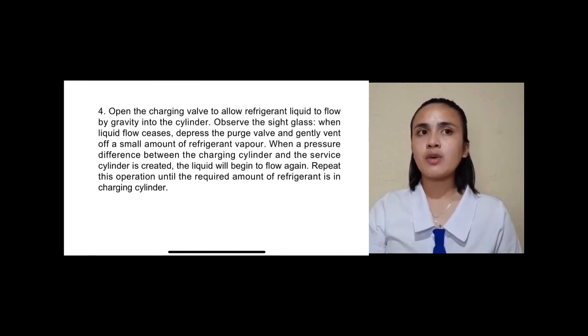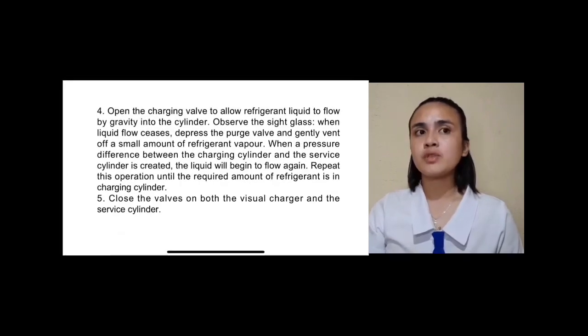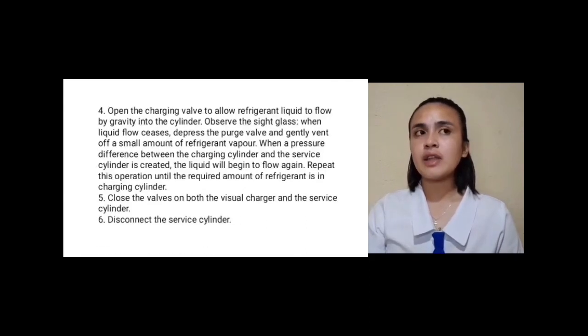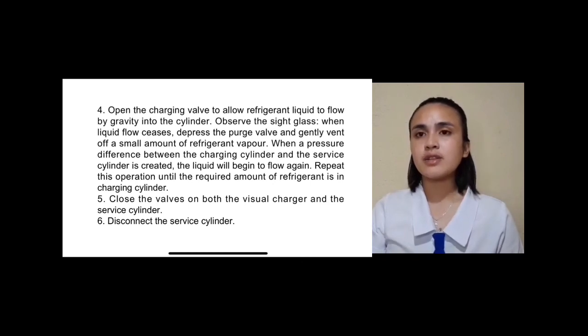Number 4. Open the charging valve to allow refrigerant liquid to flow by gravity into the cylinder. Observe the sight glass. When the liquid flow ceases, depress the purge valve and gently vent off a small amount of refrigerant vapor. When a pressure difference between the charging cylinder and the service cylinder is created, the liquid will begin to flow again. Repeat this operation until the required amount of refrigerant is in the charging cylinder. Number 5. Close the valves on both the visual charger and the service cylinder. Number 6. Disconnect the service cylinder. And we'll go to charging the system.